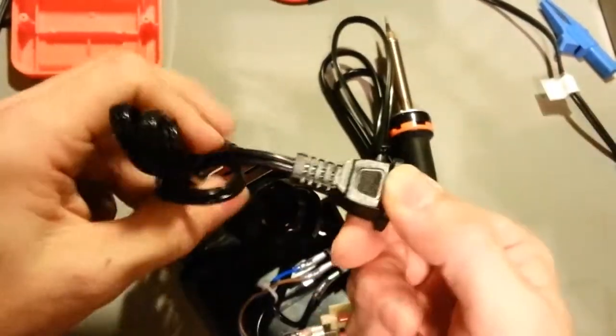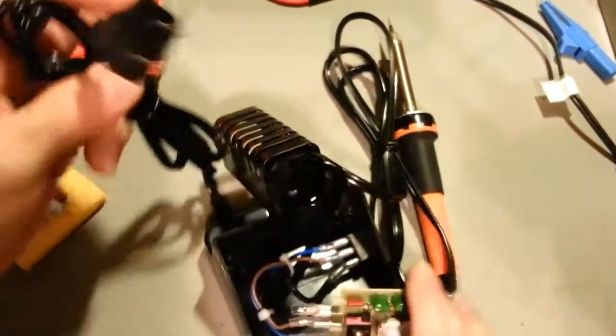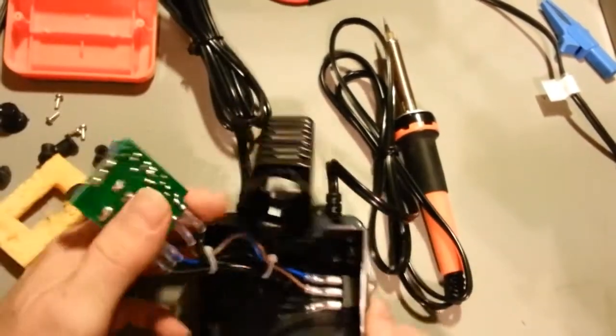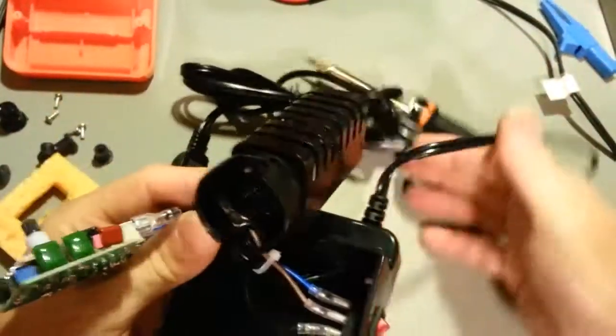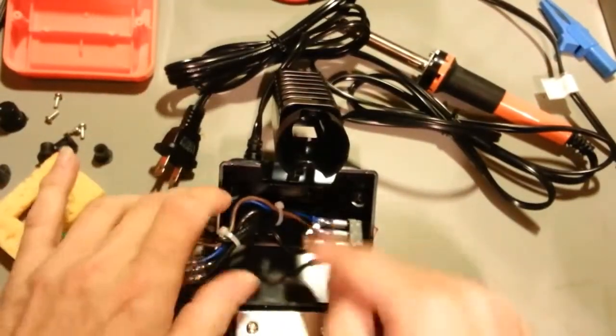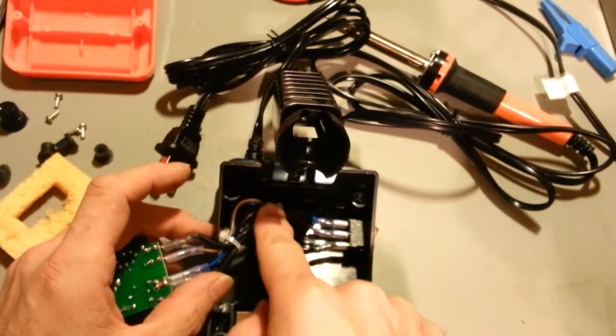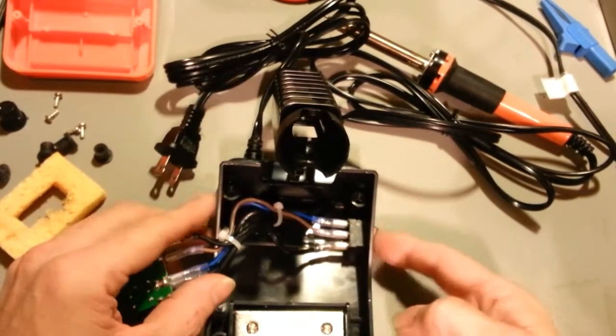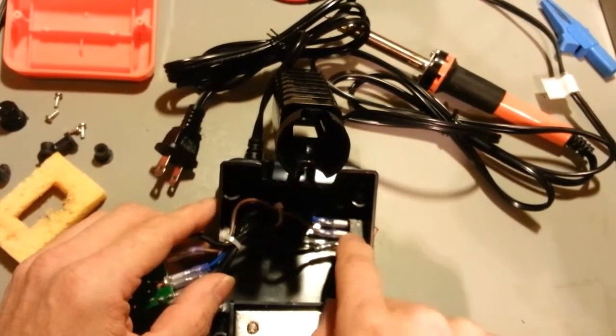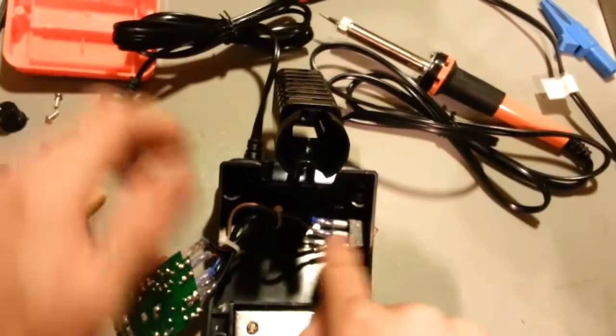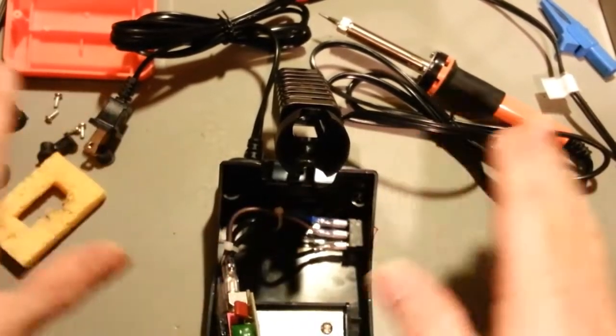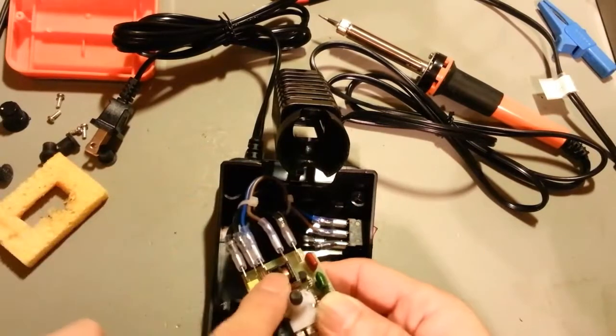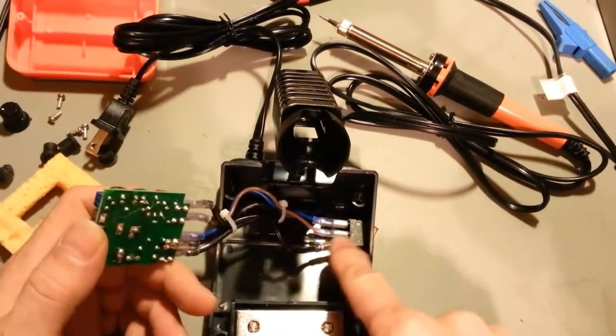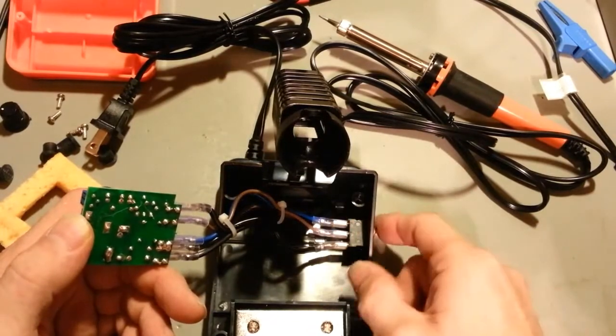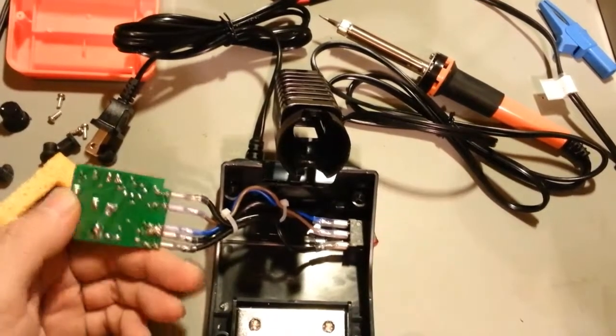So what we want to see is the hot going to the switch, not to the circuit board. Yes, that is the smooth side, so that's good. They got that right. The hot line should go to the switch. That way, when the unit is turned off, the only place there's power is the actual power cord and then that terminal, and that's it. There's no power anywhere else in here. If you run the hot up to this board, then this entire board's hot the whole way back down to this switch, and the only thing the switch is doing is switching the neutral on and off. So they got that right.